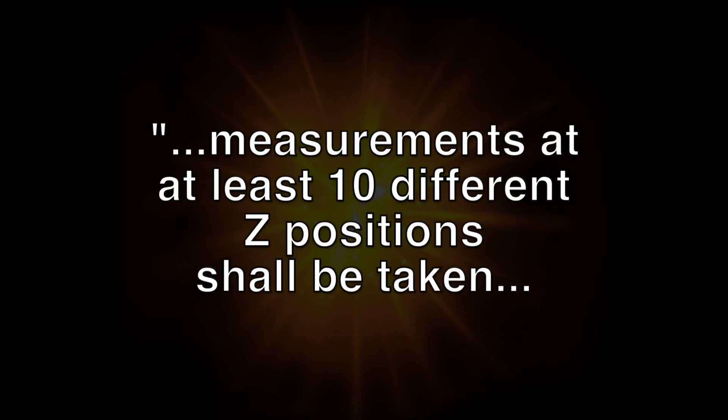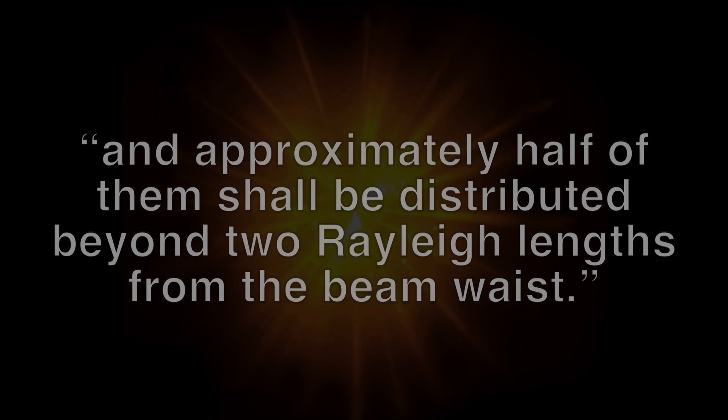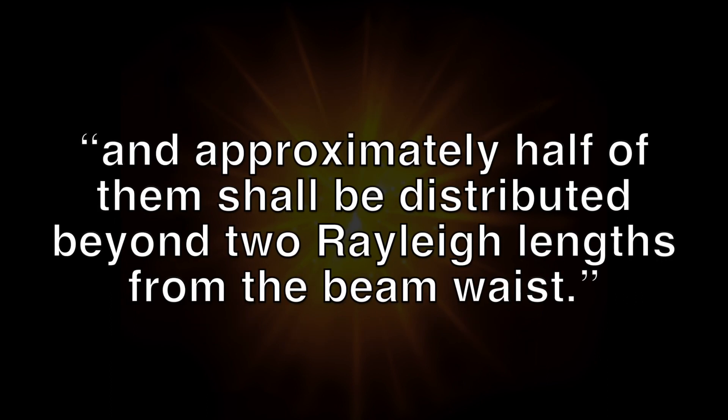As the ISO document 11146 states, measurements at at least 10 different Z positions shall be taken. Approximately half of the measurements shall be distributed within one Rayleigh length on either side of the beam waist and approximately half of them shall be distributed beyond two Rayleigh lengths from the beam waist.